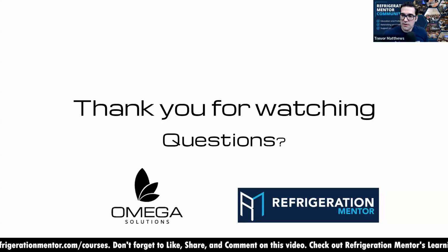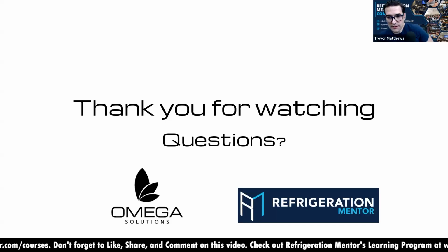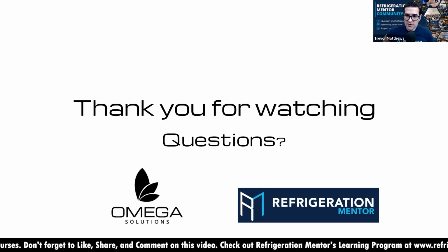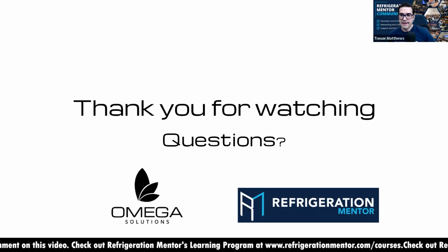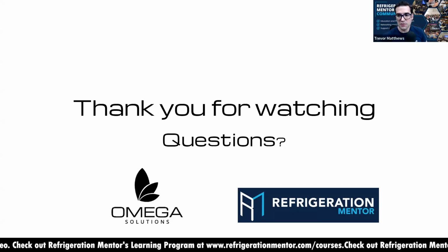So there was one question by Andrew Freeber, a good friend of mine, been in tons of training, ambassador of the Refrigeration Mentor community, and this would go back to the oil. In the transducer, what would you recommend if you do get oil in the transducer? And he answers, I feel like something needs to change, because if it happens once, it most likely happens again.